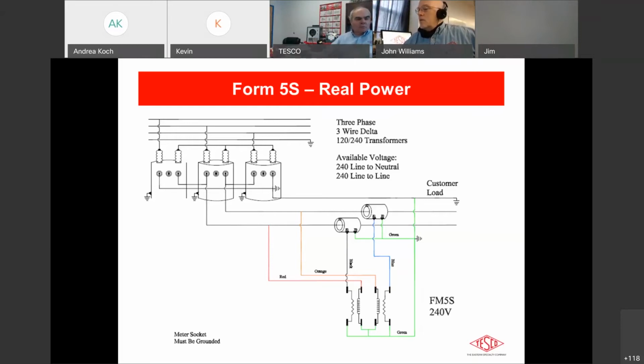The thing about the 5S in terms of meter testing, and folks here know that this is the one that I complain about most, is that the 5S is different than all the rest of the meters in that it has a potential coil where every other polyphase meter would have a current element. And that might not seem to be a big deal, but in the days before we did a lot of electronic switching and we had computers and so forth in our test boards, it became a relay connection nightmare for us, because typically for every other meter form, we can connect our current transformers right to the A phase, the B phase, and the C phase current elements where they would normally lie on every other meter.